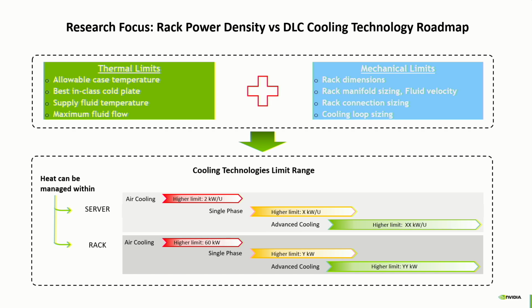The other area of research we're looking into is the next generation. We've changed the world from air cooling to liquid cooling—what happens next? Is single-phase liquid the end of the story? If we go from the 130 kilowatt rack we're releasing with NVL72 to 200, 300, 400, 500 kilowatts, is there a limit? Can I go to a megawatt rack?